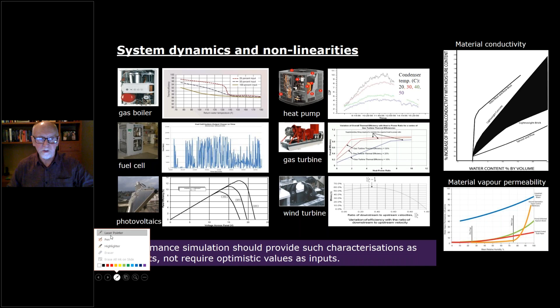So performance simulation should provide these characterizations as outputs. They're not required as optimistic input values. If you want to use a simulation program and say, I am going to fix the COP, you can do that, but you've then got to declare to the world when they see the results that you've fixed the COP, and the results are only true for that. A simulation program should not require you to input optimistic values - it should tell you how these systems will actually operate in practice and what efficiencies you'll achieve.